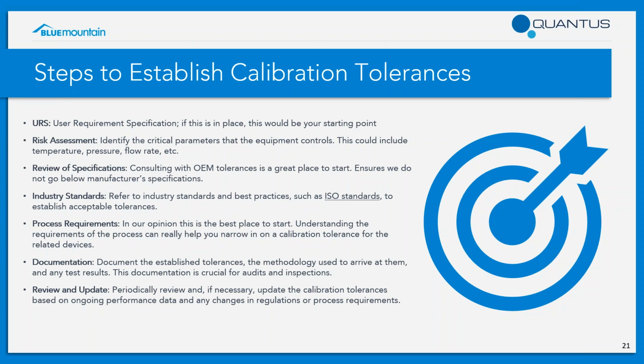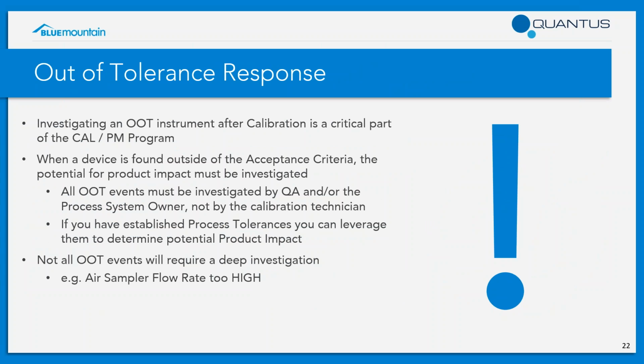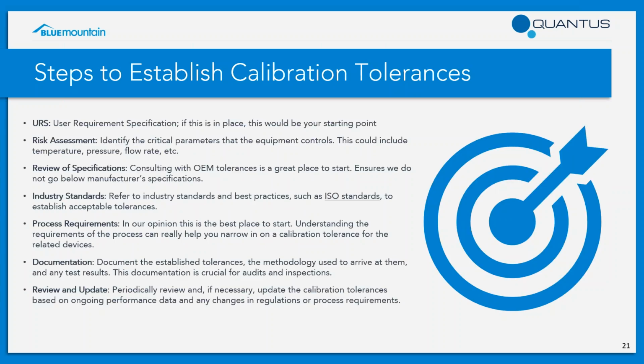You're going to want to periodically review these tolerances as a good practice. It is rarely exercised, but if you're experiencing a lot of out of tolerance events, this might be a good time to review the applied acceptance criteria. And Ryan, I just want to add to this, when we're looking at tolerances, if we don't know the process tolerance, I've seen many use the manufacturer's tolerance of the instrument. And typically what you'll experience is a lot of out of tolerances at that point. So again, think about it and then have a discussion.